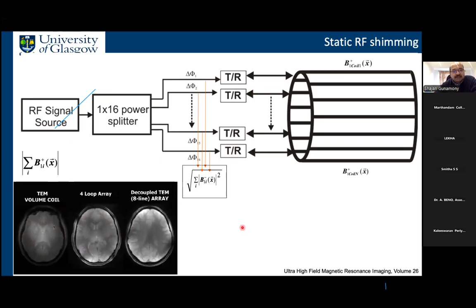So the modern scanners look like this. You have multiple of these amplifiers. We have an array of amplifiers. Suppose we have an 8-channel system, or an 8-channel transmit array coil, then we will have 8 of these amplifiers operating in parallel. And then we can influence the amplitude and phase of the current to each of these coil elements. So we can also imagine this in a clinical scanner. You will have one amplifier like this, where in an ultra high field scanner you have 8 or 16 of these. So you can imagine how complex the ultra high field scanner is, because it's equivalent to 8 or 16 of the clinical scanners working in parallel. So it's really complex, and it's really expensive as well.